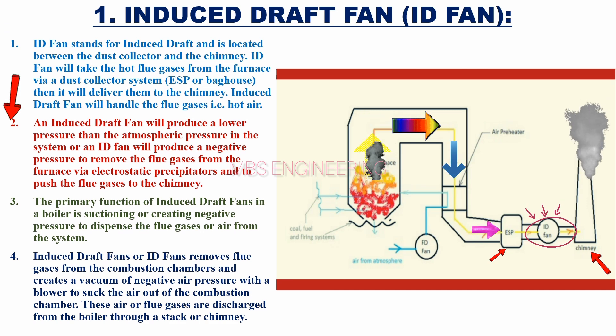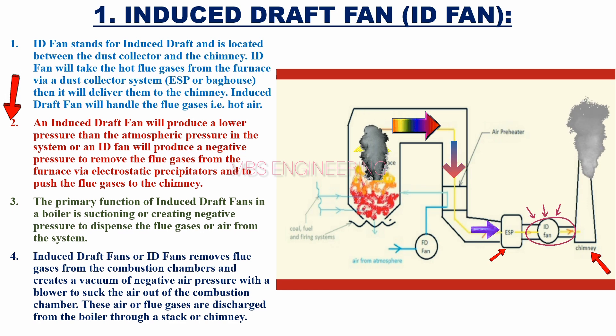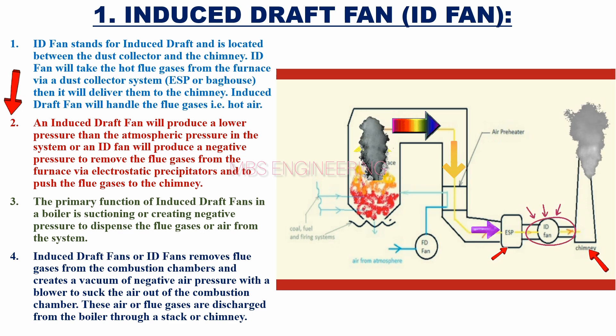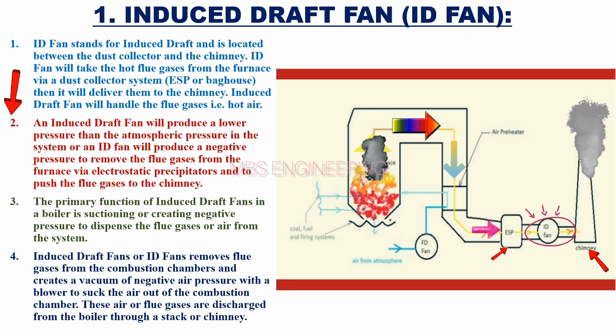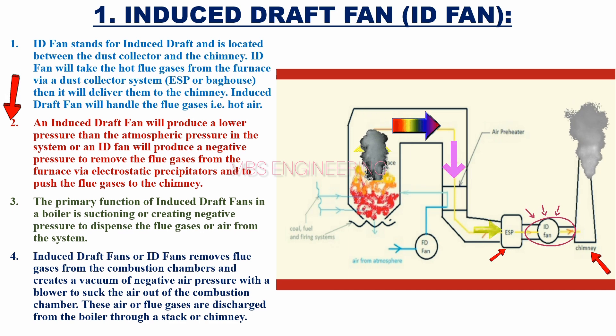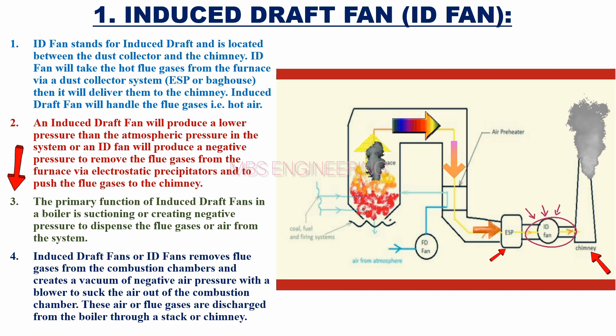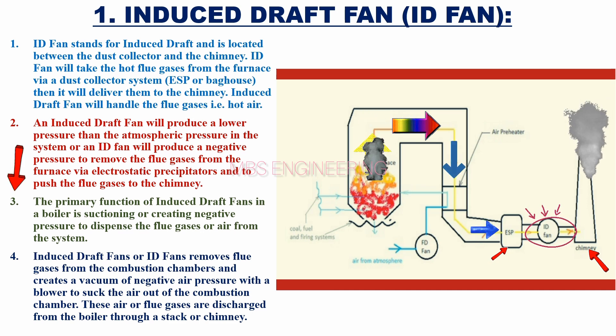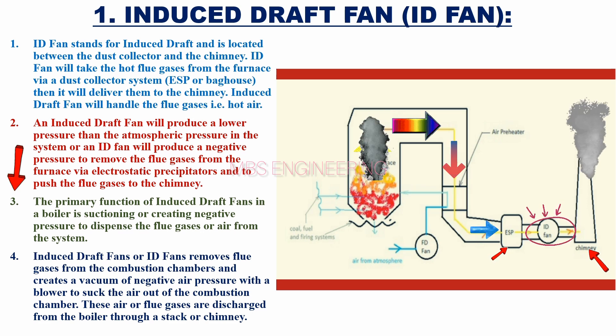The ID Fan will produce lower pressure than the atmospheric pressure in the system, or in other words, it will produce negative pressure to remove the flue gases from the furnace via electrostatic precipitators and push the flue gases to the chimney. The primary function of Induced Draft Fans in a boiler is suction — creating negative pressure to dispense the flue gases or air from the system.